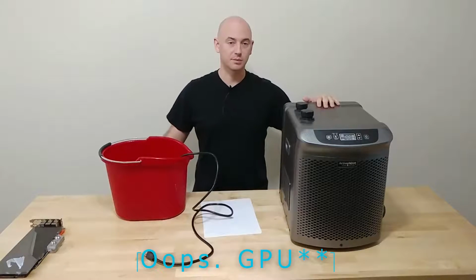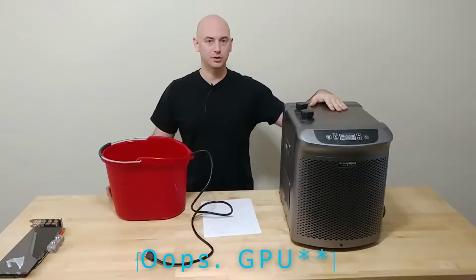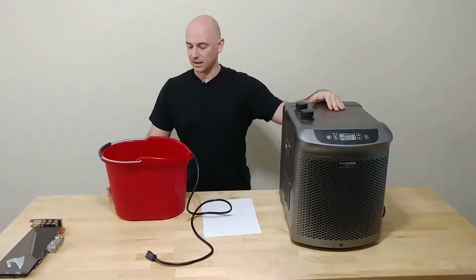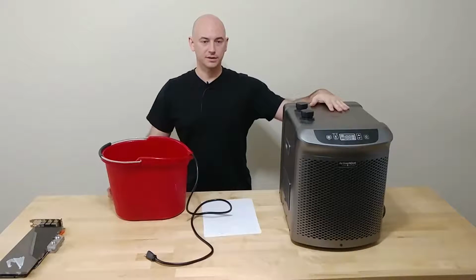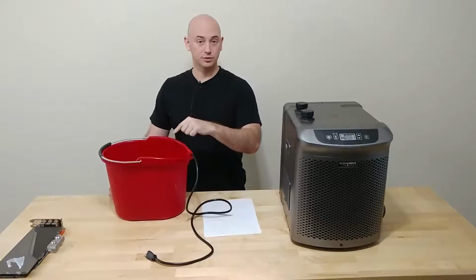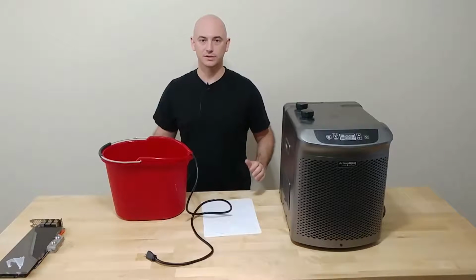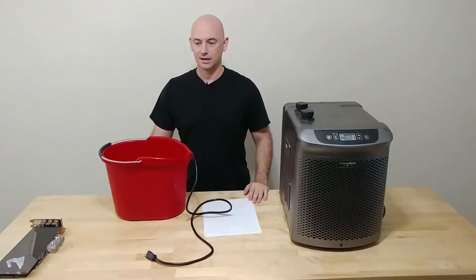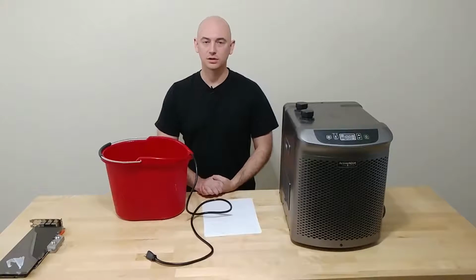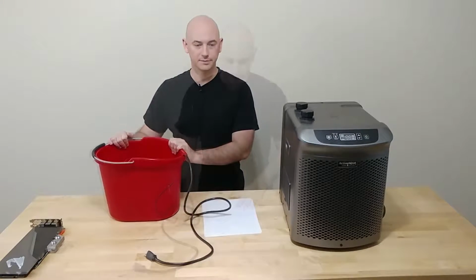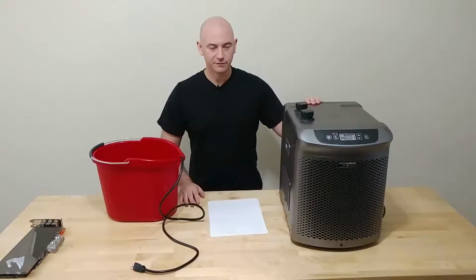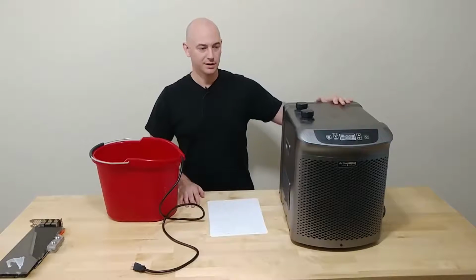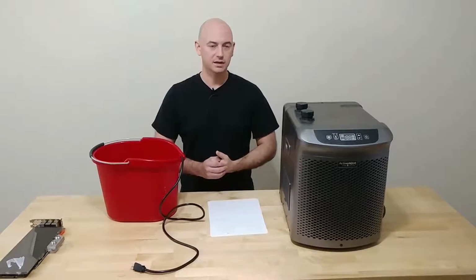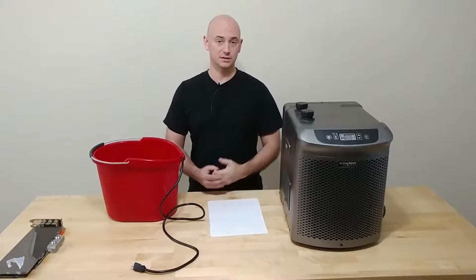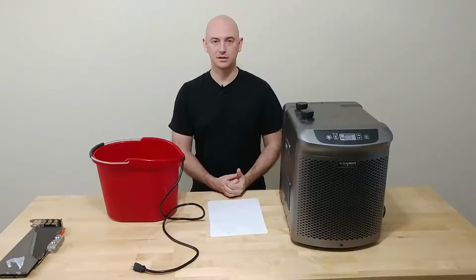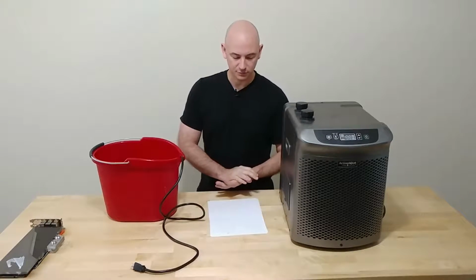The chiller has a thermometer built into it, so I can see the temperature of the water going right into the GPU. That's how I would monitor it through the chiller, and I would monitor the temperature of the water in the bucket. If those were pretty close, that means the water was stabilized, and I would take the next reading. And it only took a few minutes because this volume of water is pretty small. And this chiller itself is about 5 amps. It does a 1/4 horsepower, and that's enough to chill the water. I got it down to about 7 degrees before we started seeing condensation, and at that point I had enough data. So now, on to the data, what did it look like?